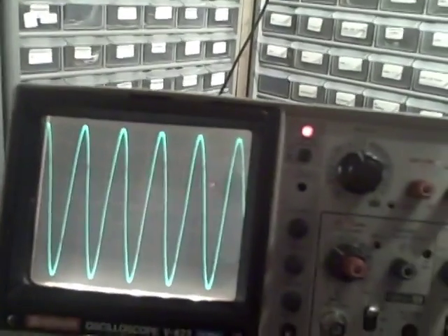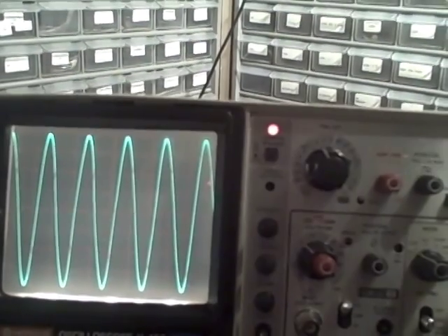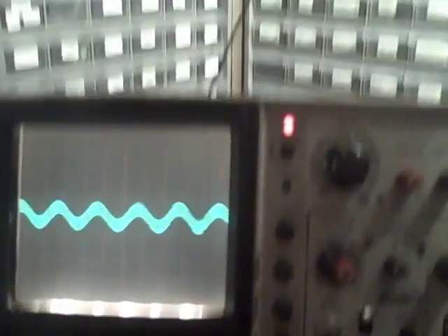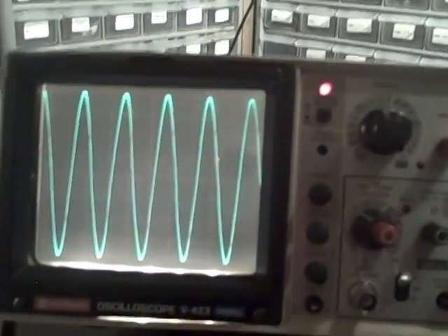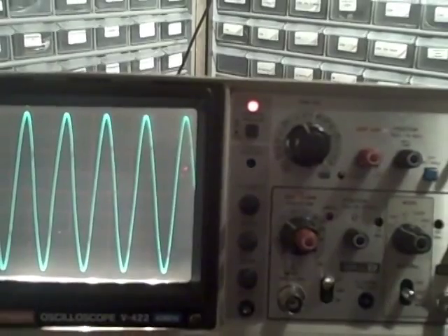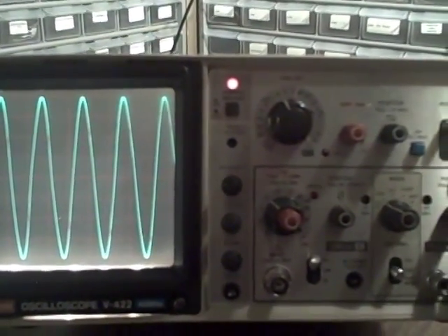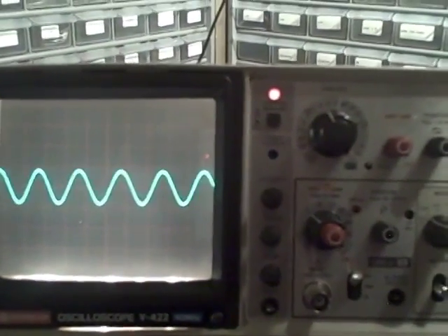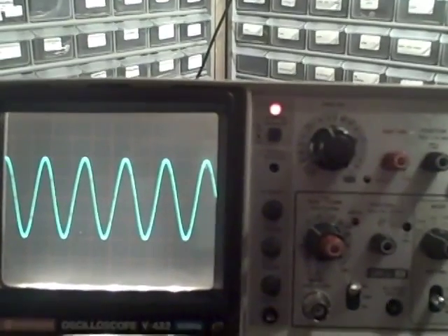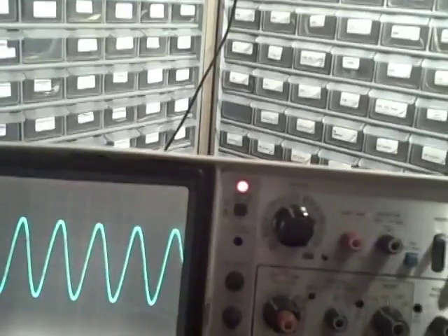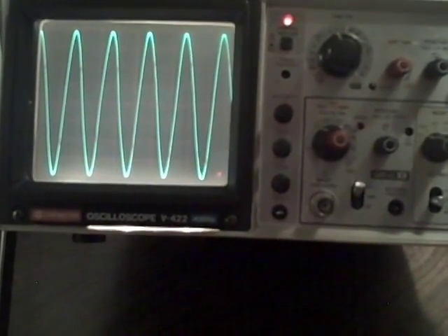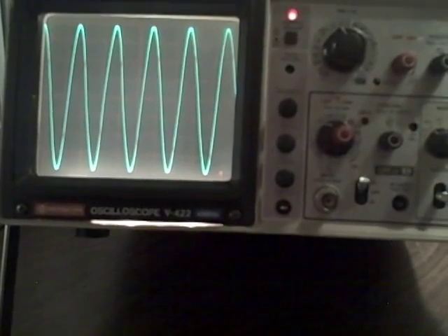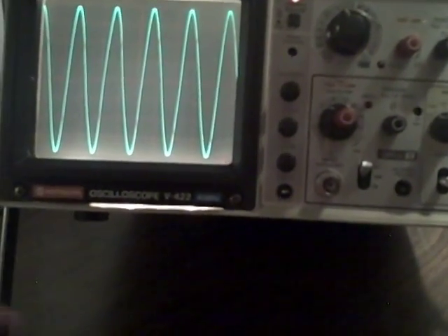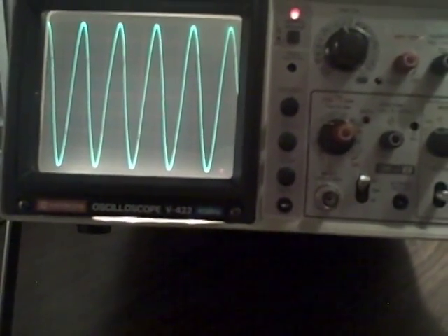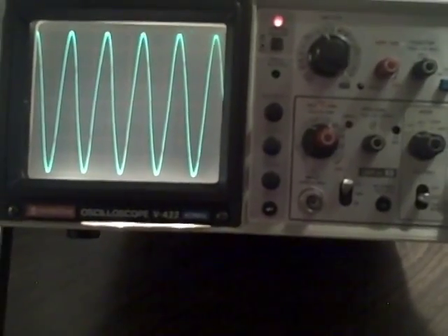Let's go ahead and take ourselves to the 100 millivolt per division scale and take off our divide by 10 now. And once again we see ourselves plus or minus full scale, and that's as it should be. And then finally let's hit the last range we're going to check, put ourselves back on divide by 10. We are on the 20 millivolt per division range. I want 800 millivolts from my generator, so let's take care of that. We are on the 20 millivolt per division scale. We see ourselves up 4 divisions, that's 80 millivolts. Since we're dividing by 10 through our probe, that means we have 800 millivolts coming in, and that's what our generator is providing.